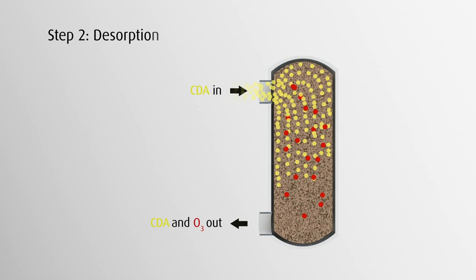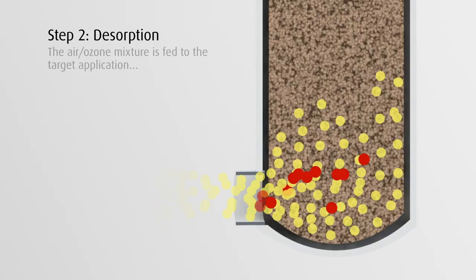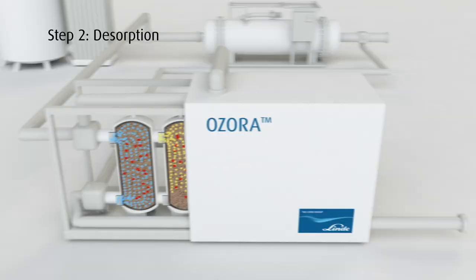Then, in the desorption step, compressed dry air flows through the bed and releases ozone from the pores. The air-ozone mixture is then supplied to the target application at a stable preset concentration and flow rate.